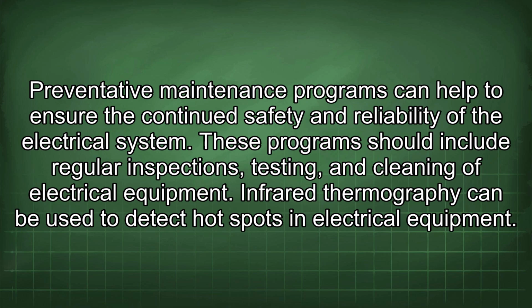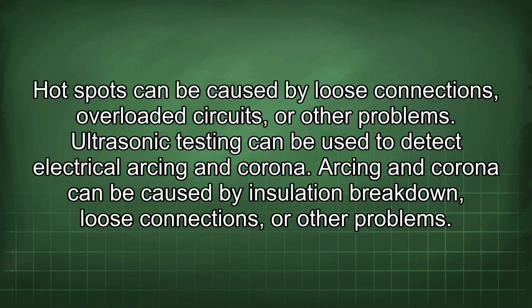Preventative maintenance programs can help to ensure the continued safety and reliability of the electrical system. These programs should include regular inspections, testing, and cleaning of electrical equipment. Infrared thermography can be used to detect hot spots in electrical equipment. Hot spots can be caused by loose connections, overloaded circuits, or other problems.